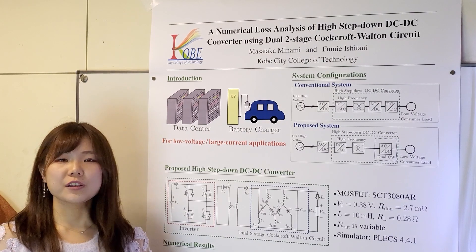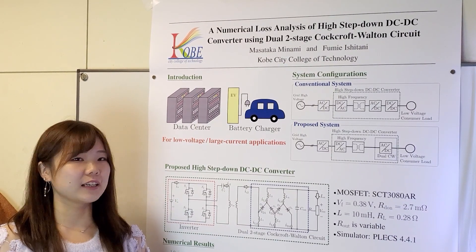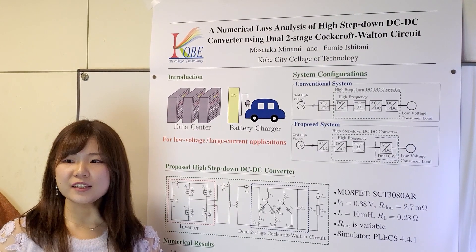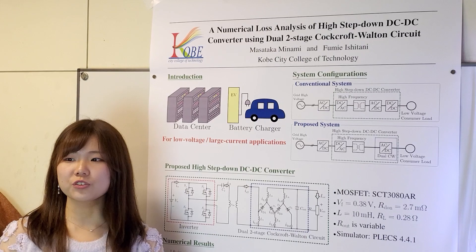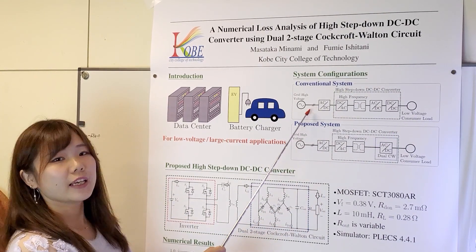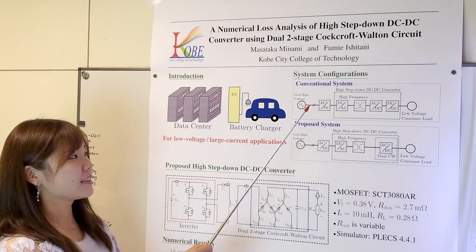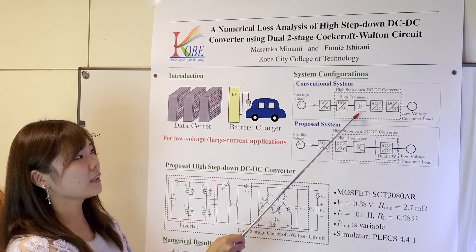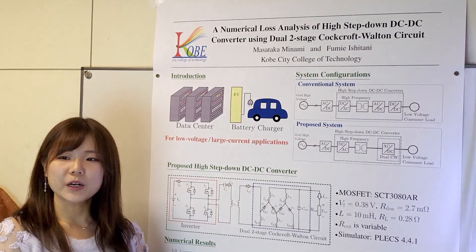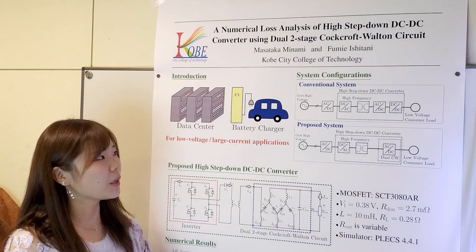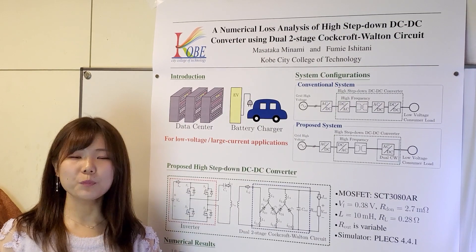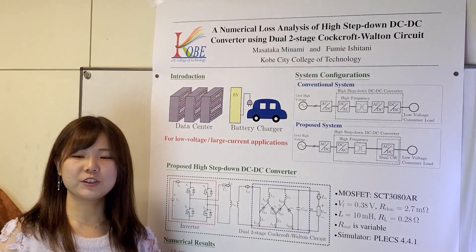In order to supply electric power to low-voltage and large-current applications from power-grid system, it is necessary to use multi-stage connection transformer like this conventional system. In this conventional system, there are inverter, transformer, rectifier, and DC-DC converter. However, multiple transformer makes lots of loss by active components and it causes lower efficiency.